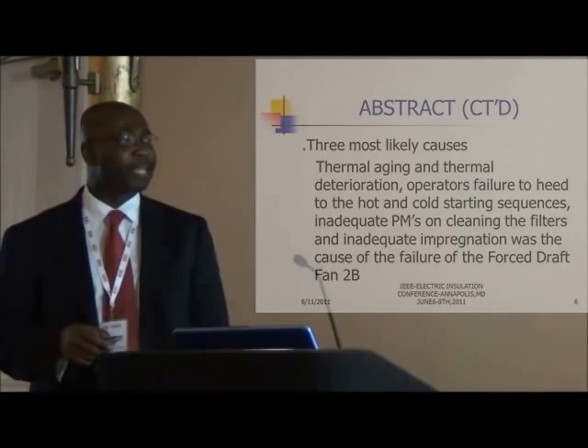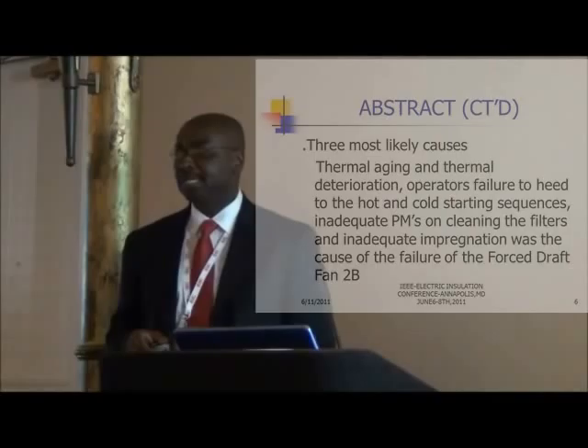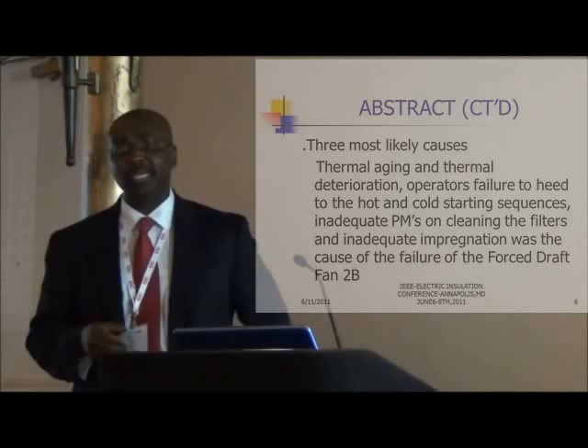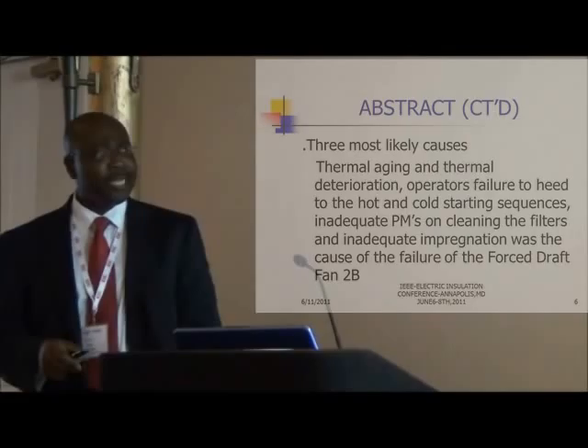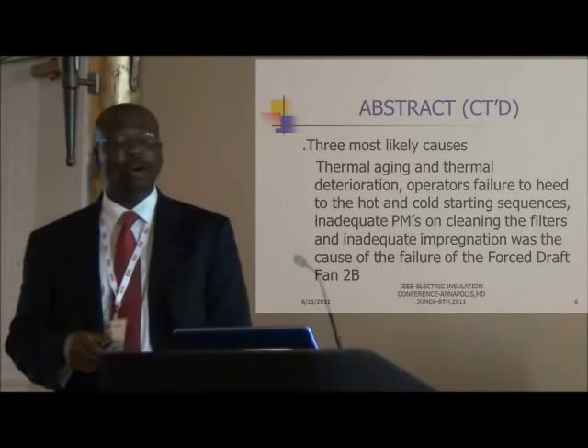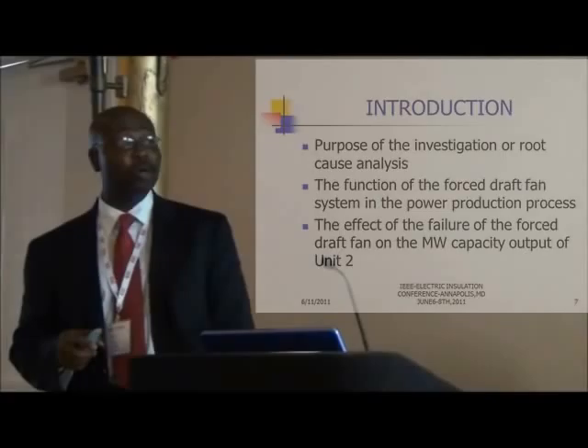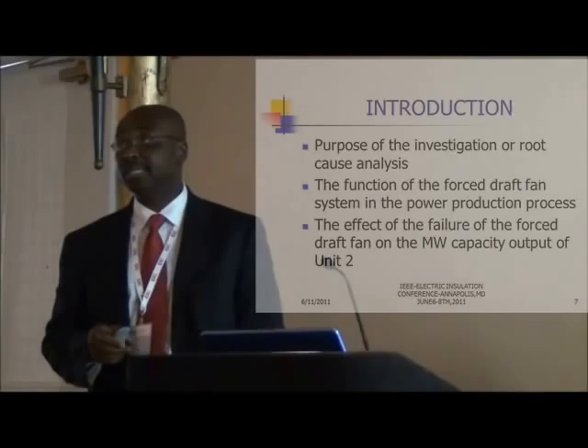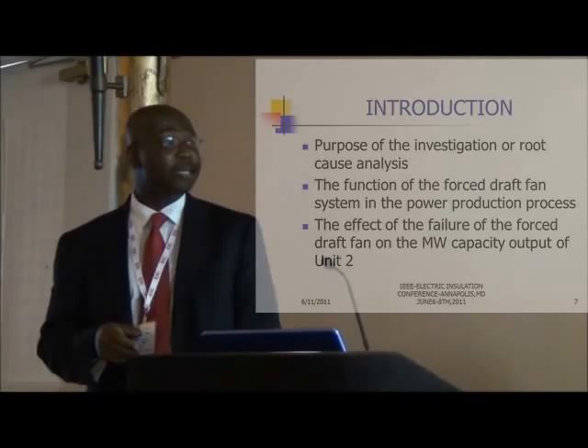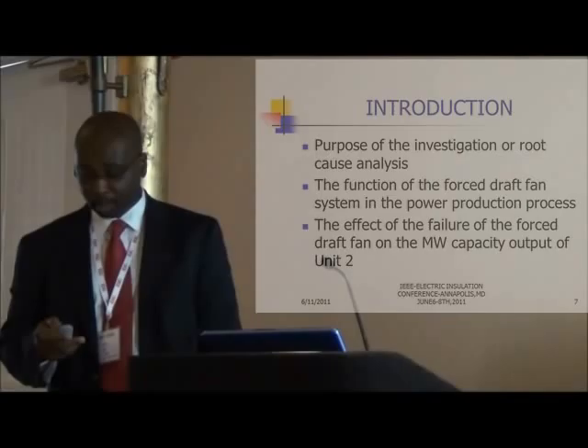The machine environment creates a lot of stresses that can age motors and cause them to fail. On the electrical side, the expansion of the motor — specifically the copper — causes differential expansion between the insulation and the copper, which leads to gradual degradation of the insulation. When we did the root cause analysis, we found three most likely causes: thermal aging and thermal deterioration, operator failure to adhere to the cold and hot starting sequence, and inadequate PMs for cleaning the filters.